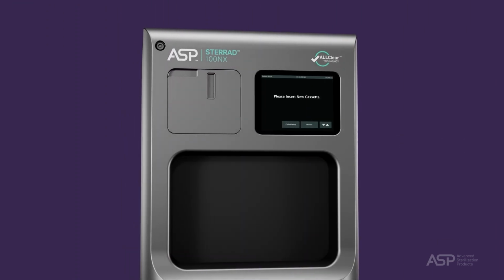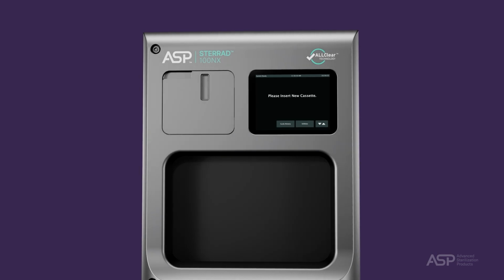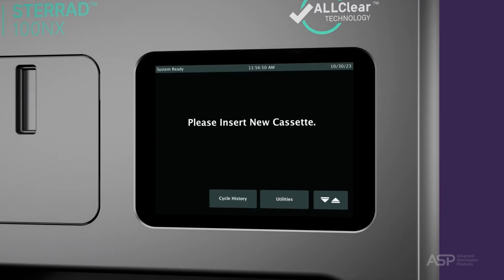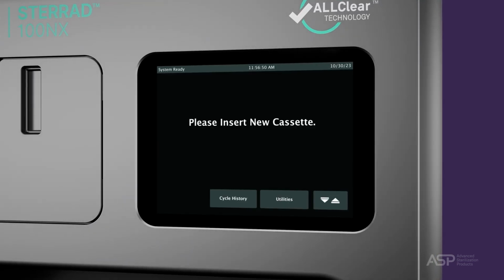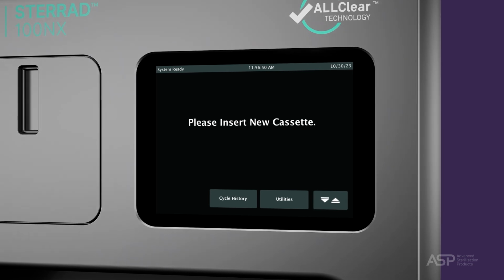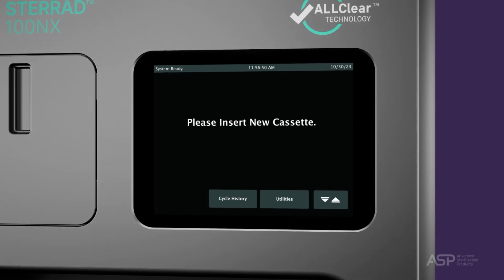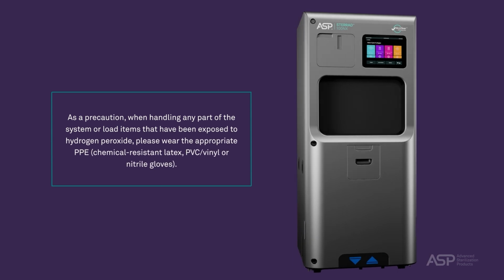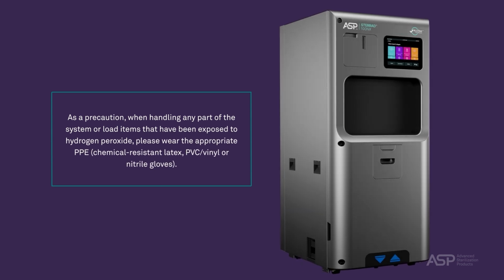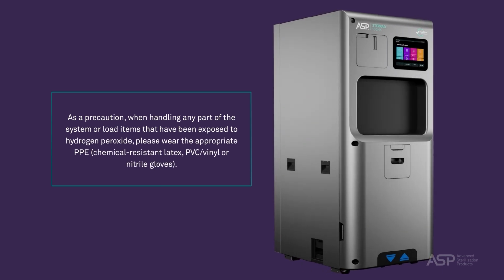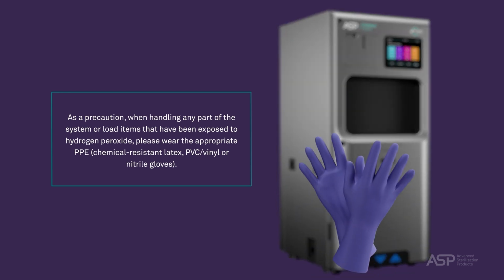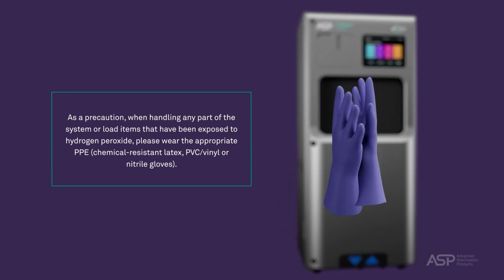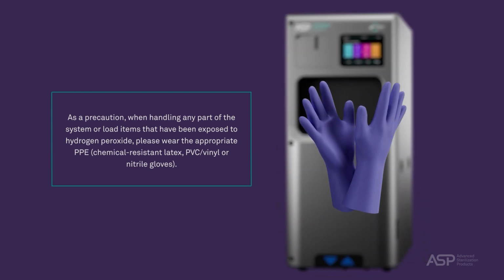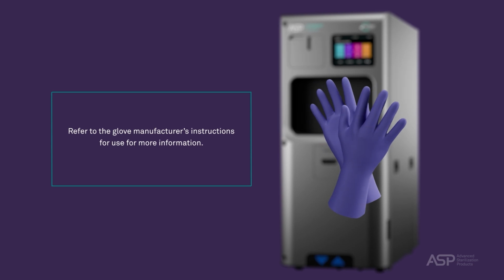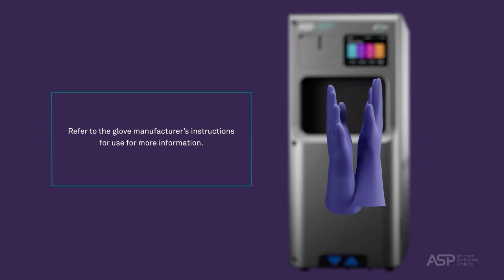When a new STERRAD 100NX sterilizer cassette is required, when the cassette in the sterilizer is expired, or if there is no cassette installed, the screen will display the message, "Please insert new cassette." As a precaution, when handling any part of the system or load items that have been exposed to hydrogen peroxide, please wear the appropriate PPE, chemical-resistant latex, PVC/vinyl, or nitrile gloves. Refer to the glove manufacturer's instructions for use for more information.